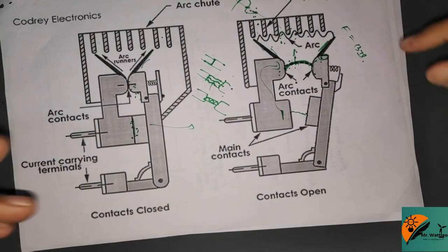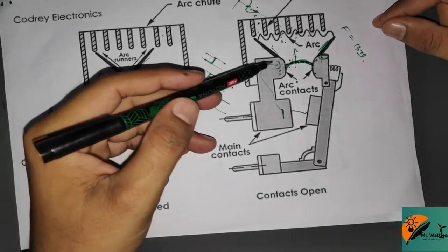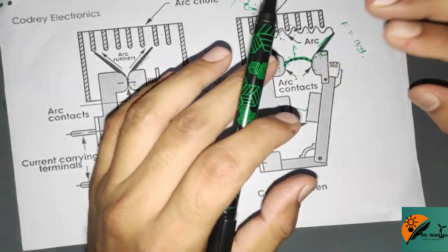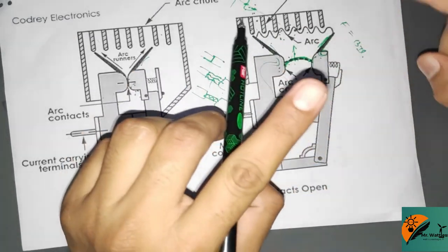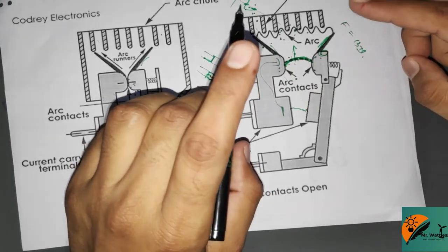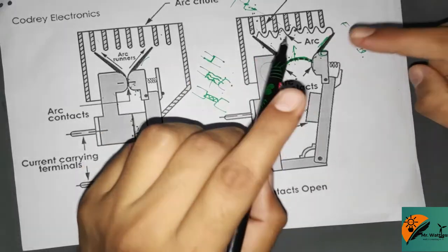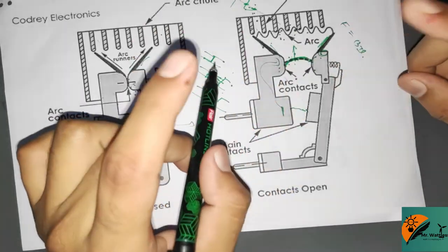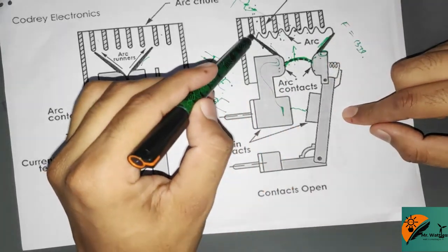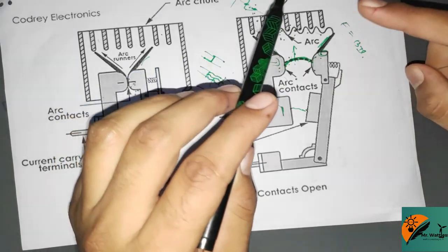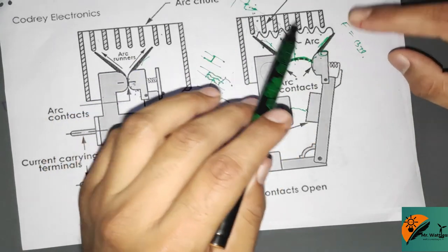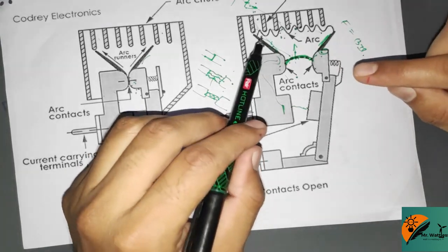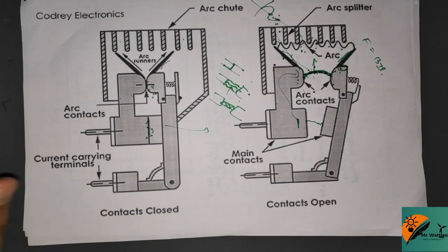This force assists in moving the arc upward. For systems having low inductance, the arc gets extinguished before reaching the extremity of the runners, because lengthening of the arc increases the voltage drop, which is insufficient to maintain the arc. For high inductance circuits, if the arc is not extinguished while traveling through arc runners, it is passed through arc splitters where it is cooled down. This causes effective deionization by removing heat from the arc, and the arc is extinguished. This type of circuit breaker is commonly employed for industrial switchgear and auxiliary switchgear in generating stations.